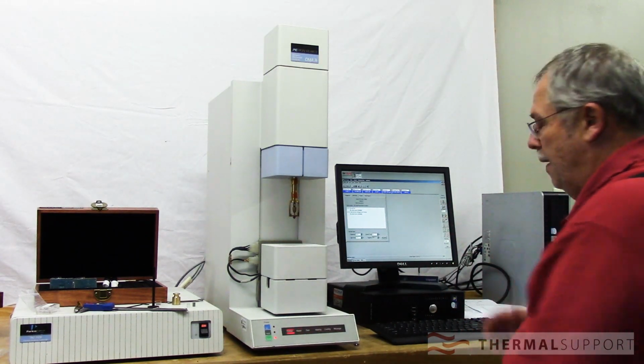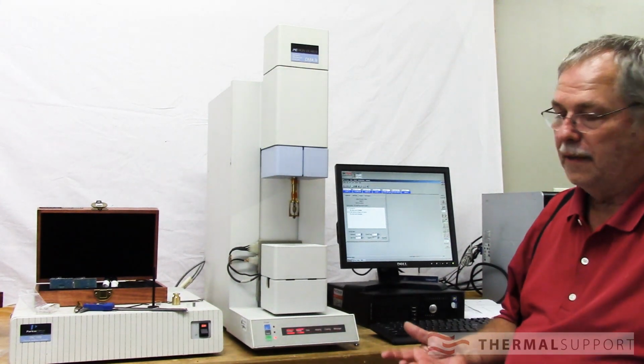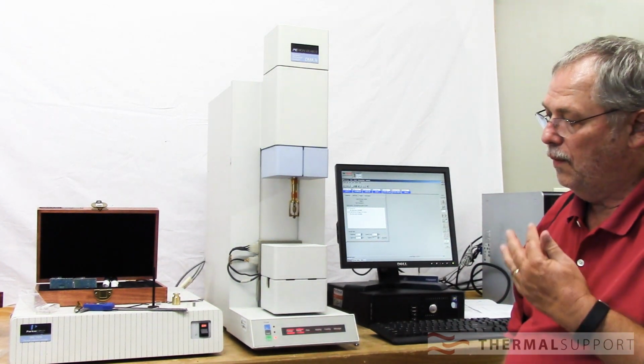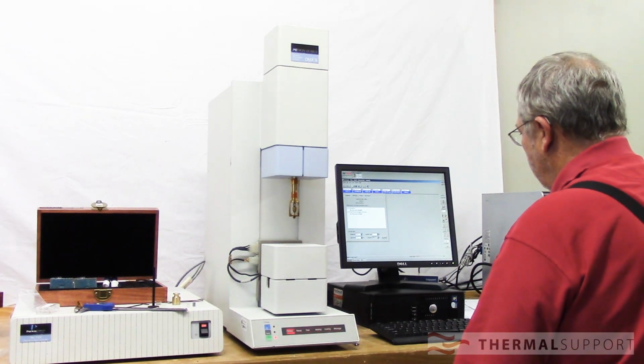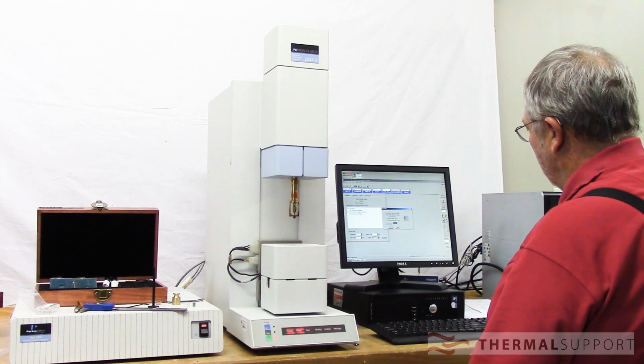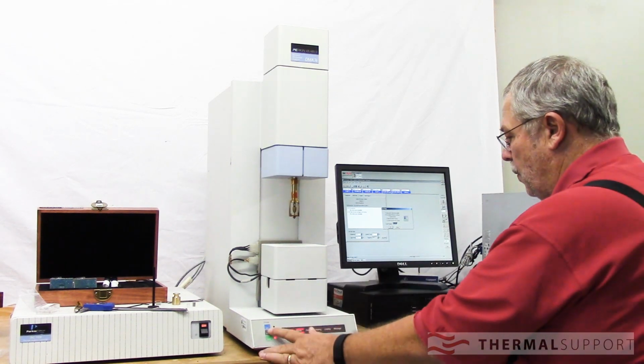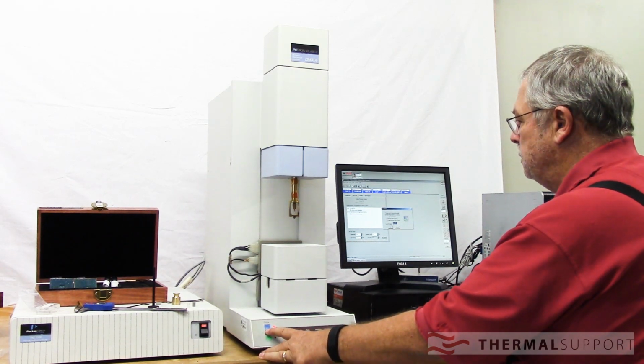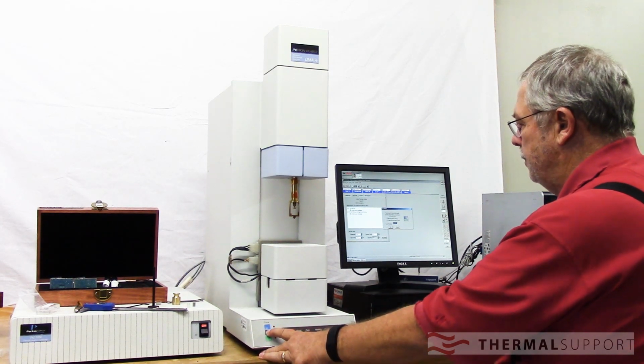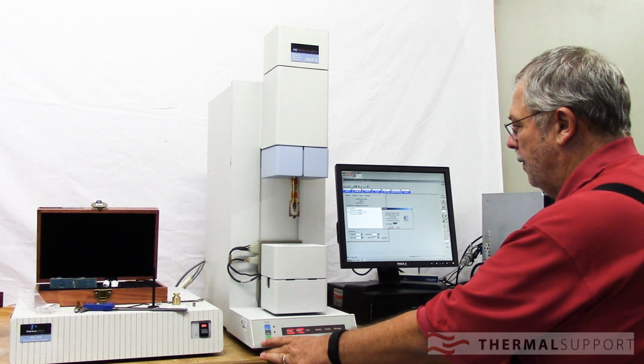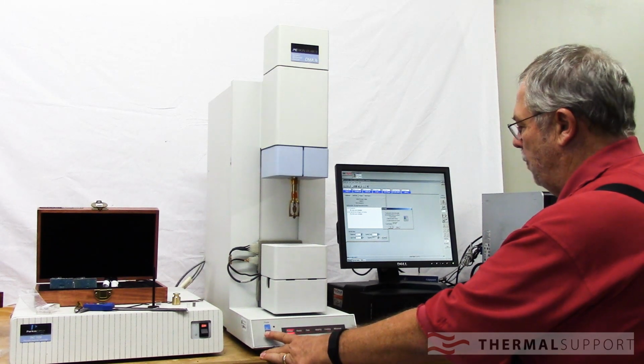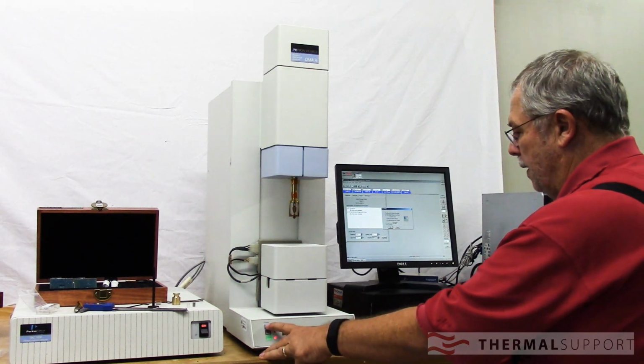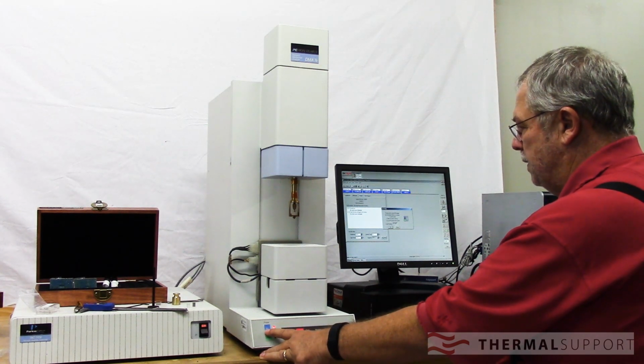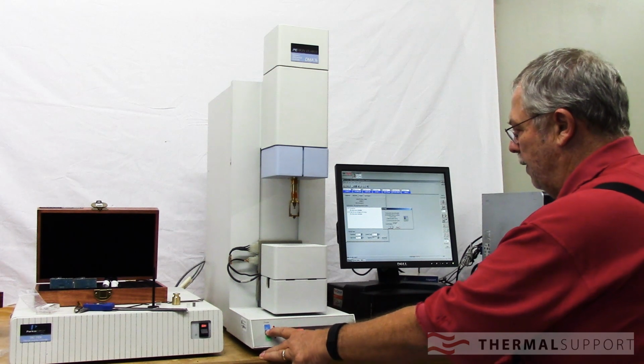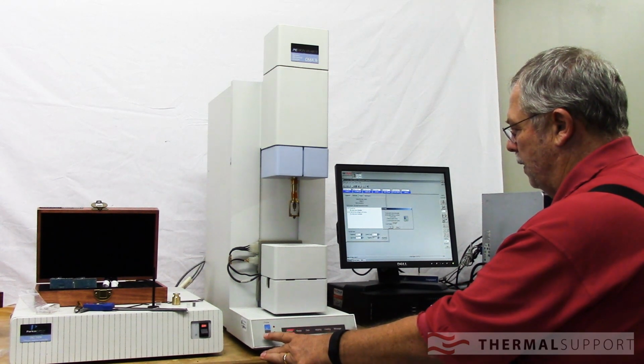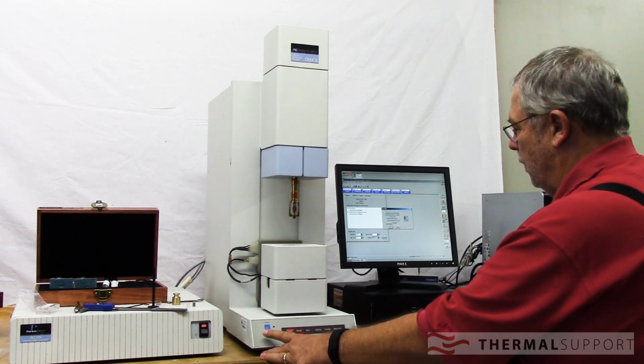Now, you know what we need to do, because we just did it. We don't have this hardware on. We don't know what the weight of the probe is. We need to compensate for that. So we're going to go back into our tare probe. We're going to go up all the way. And we've seen these where if you go up all the way, that's 10.429. They'll stick at the very top, but it'll work perfectly, meet every spec on Earth when you're down in your operating range. And can you run like that?